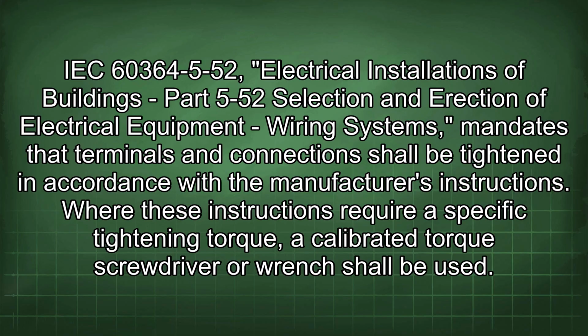IEC 60364-5-52, Electrical Installations of Buildings, Part 5-52, Selection and Erection of Electrical Equipment, Wiring Systems, mandates that terminals and connections shall be tightened in accordance with the manufacturer's instructions. Where these instructions require a specific tightening torque, a calibrated torque screwdriver or wrench shall be used.